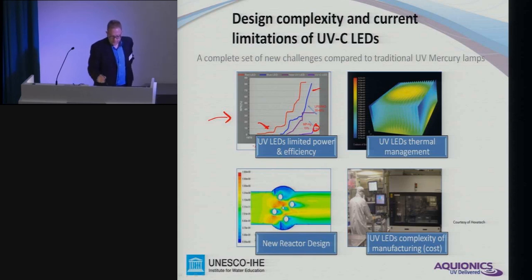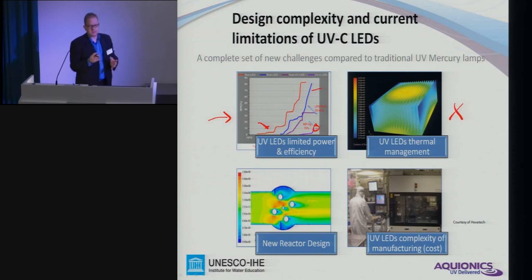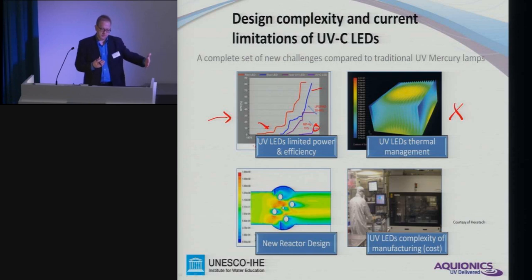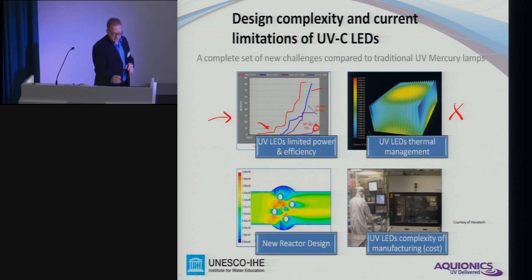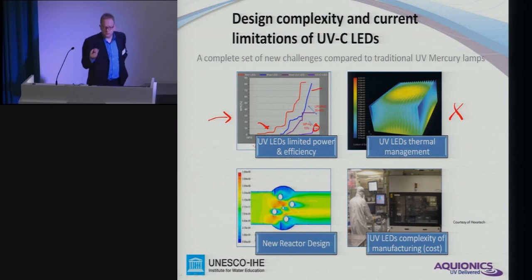Another very important thing is thermal management. Due to inefficiency, a lot of heat is created — not on the side irradiating light into the water, so the medium will not be warmed up, but on the back side, the electronics will warm up. You need to get rid of that heat and manage the LED from a thermal point of view to ensure lifetime is achieved. Obviously the reactor design is very important, and due to the different geometries, it will be different from a traditional UV system.